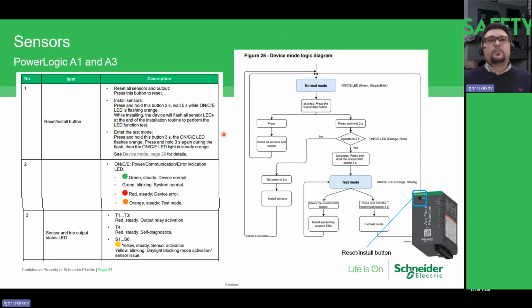Here is also an explanation of how you configure this device. At first you need to read the manual a little bit, but after that it's quite easy. When you have installed all your sensors, connected your whole system and powered on, of course the error lights will be active because the system doesn't yet match your application. You configure it by pressing and holding this push button once. You will see the button start to blink yellow. After that you can release it, and the system will read all connected sensors, all connected units, and the configuration of the DIP switches, and install by itself. So you don't need to do any action. You just push the button, and the system configures and installs by itself.